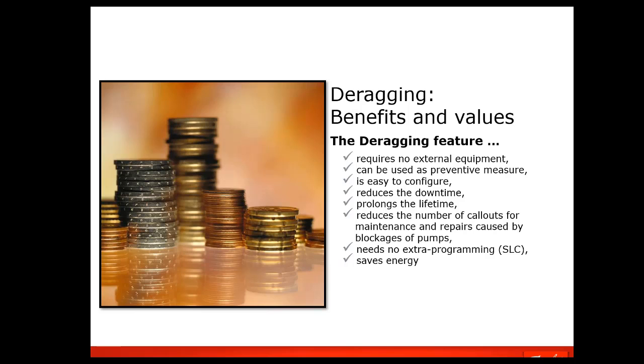It does reduce downtime. We have had this in the drives for I want to say almost 10 years now, actually. And it has been used in many wastewater applications around the globe. It prolongs the lifetime of the pump and can reduce the number of callouts or problems or blockages in pumps. It needs no extra programming. It is a pre-canned feature in the FC202, and it can help save energy based on not trying to run high speed, trying to declog it just forward.